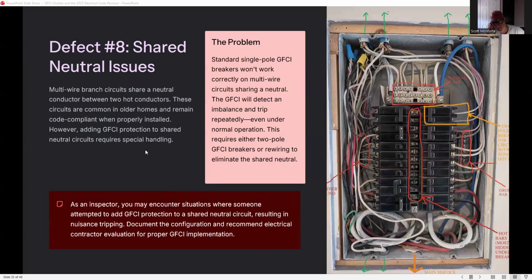Defect number 8, shared neutral issues. Multi-wire branch circuits share a neutral conductor between two hot conductors. These circuits are common in older homes and remain code compliant when properly installed. However, adding GFCI protection to shared neutral circuits requires special handling.